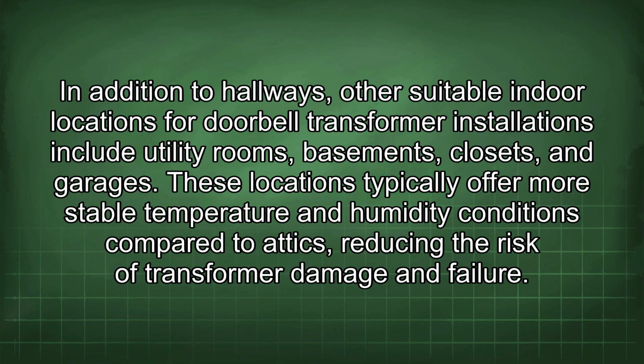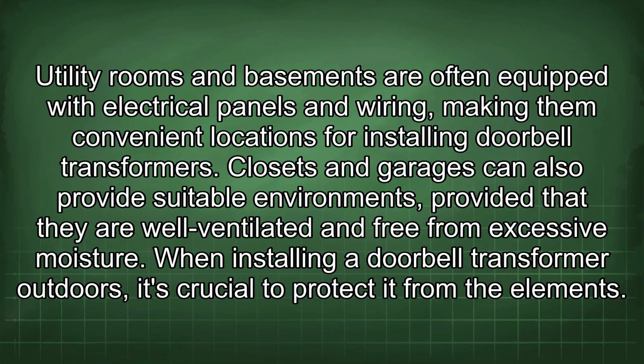In addition to hallways, other suitable indoor locations for doorbell transformer installations include utility rooms, basements, closets, and garages. These locations typically offer more stable temperature and humidity conditions compared to attics, reducing the risk of transformer damage and failure. Utility rooms and basements are often equipped with electrical panels and wiring, making them convenient locations for installing doorbell transformers. Closets and garages can also provide suitable environments, provided that they are well ventilated and free from excessive moisture.